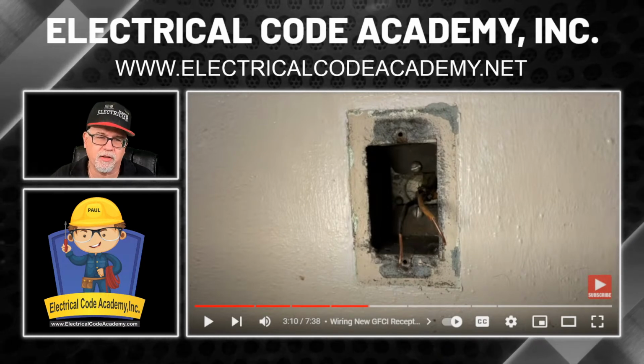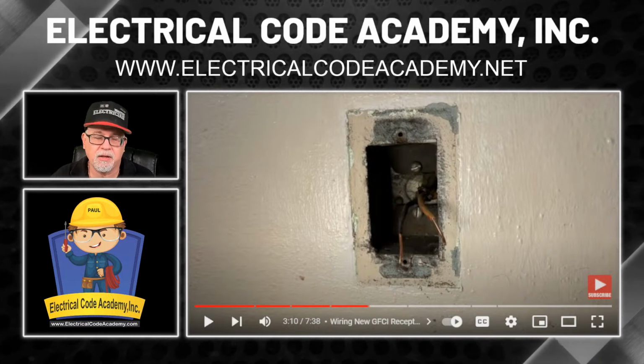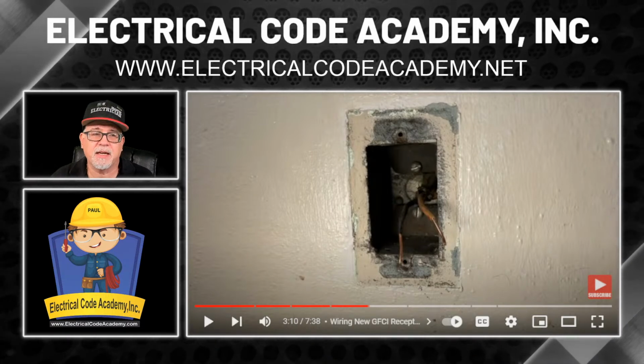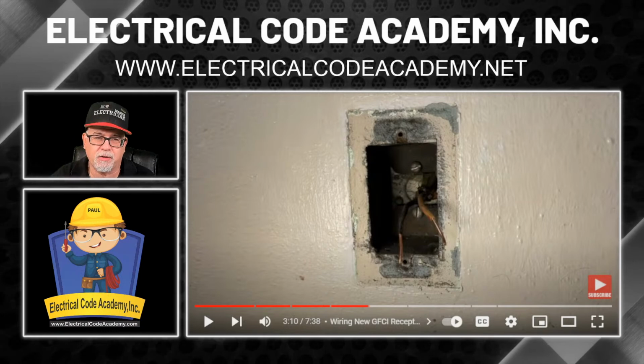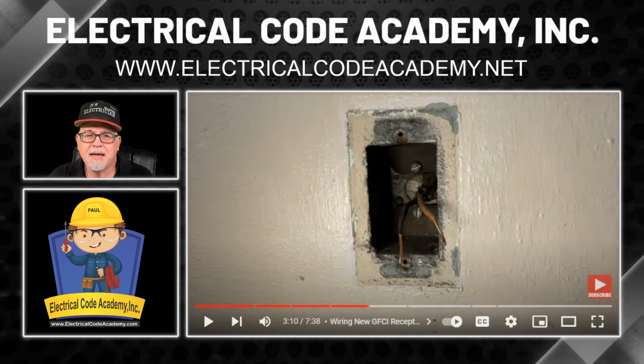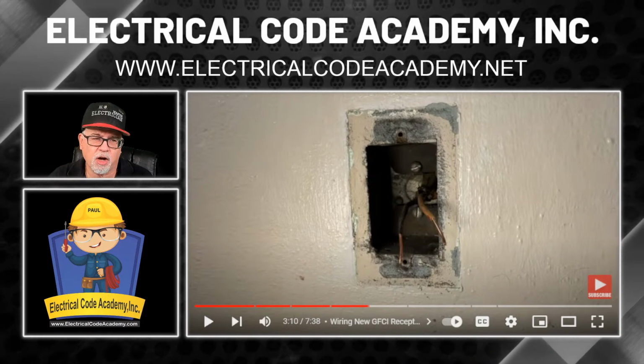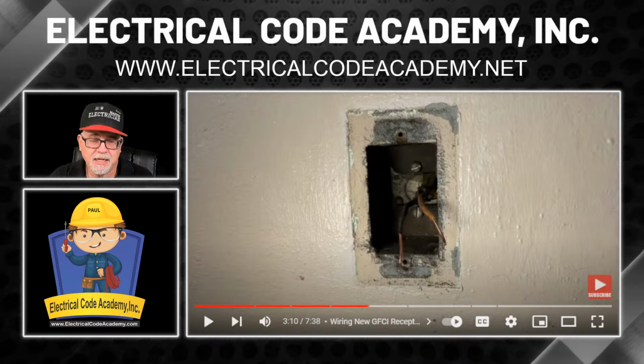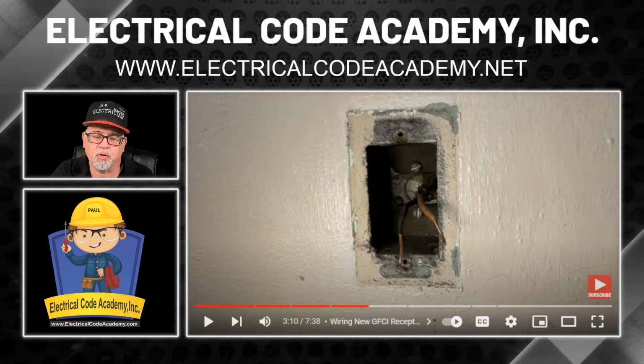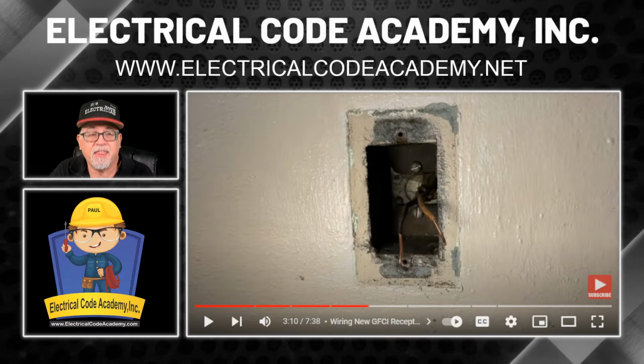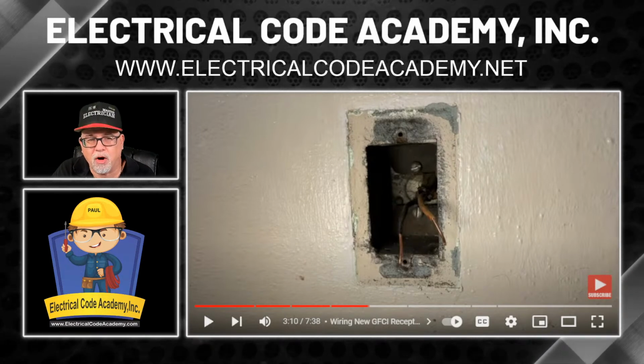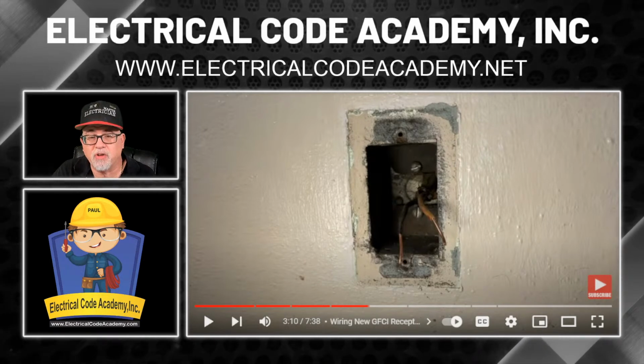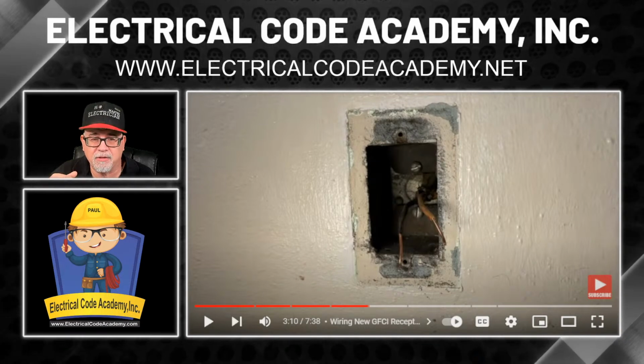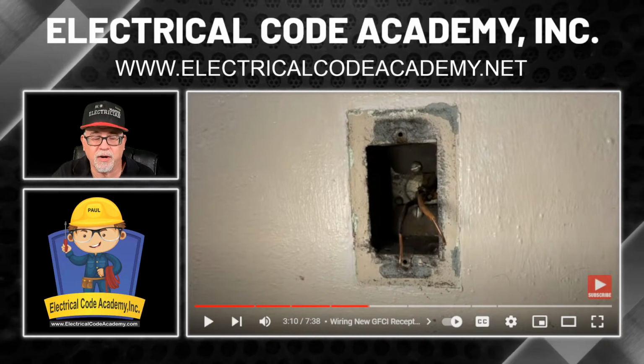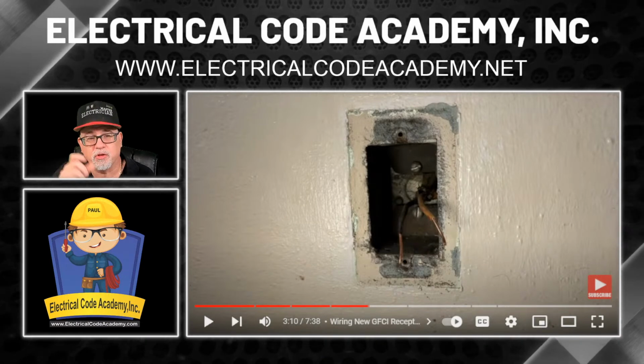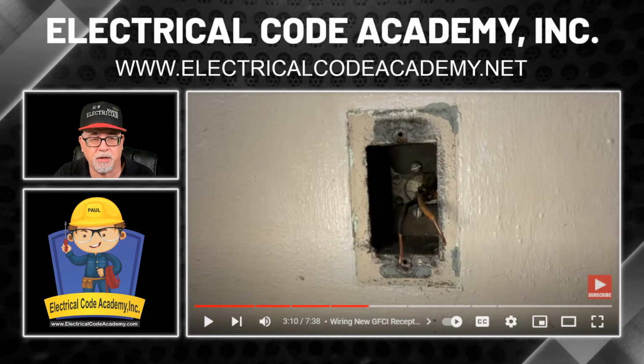Flippers want to do that all the time because close proximity to a panel, it might read out as being a connection to ground as it connects to the panel, and then they end up wanting to use it. BX was never intended for the armor to be used as an equipment ground. AC cable, which is under Article 320 of the NEC, is specifically designed to use the armor as an equipment ground. That way you don't have any equipment grounds inside of the cable assembly, okay? Because you're using the armor and you use a special fitting that's listed for use with the AC cable in conjunction with the metal box.